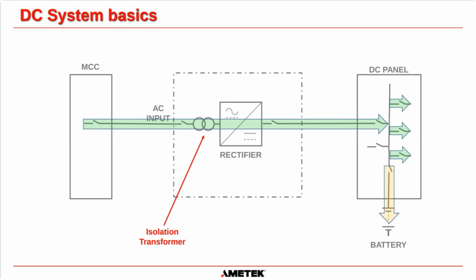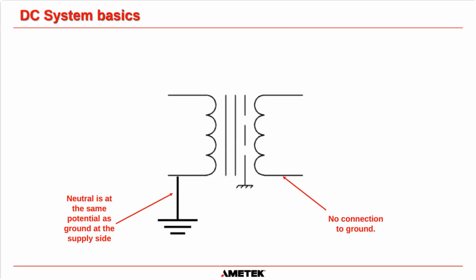But the important thing about an industrial battery charger is it should always have an isolation transformer on the input, okay? And this isolation transformer gives you galvanic isolation between the AC that's coming from your MCC, or your motor control center, or your switchgear room, and the AC on this side that goes into the rectifier. And I'll explain in the next slide why it is very important. That isolation basically allows the DC that's created by the charger to be what most people refer to as a floating DC voltage. And we'll get into that term in a moment.